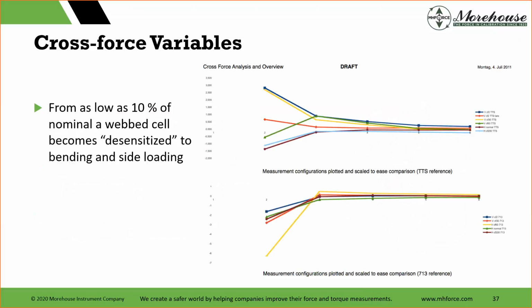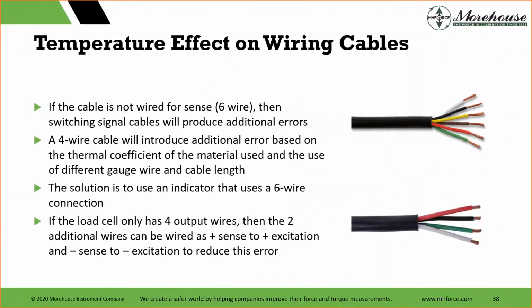On these, from as low as 10% of nominal, a web cell becomes desensitized to bending and side loading. That's why the recommendation here is towards those web type cells, if you can control what you're using for the standard cells to calibrate the torque wrenches. Additional error here: temperature effect on wiring cables. If a cable is not wired for sense 6-wire, then switching signal cables will produce additional errors. That's something to look at in your meters. It's something we talk about.